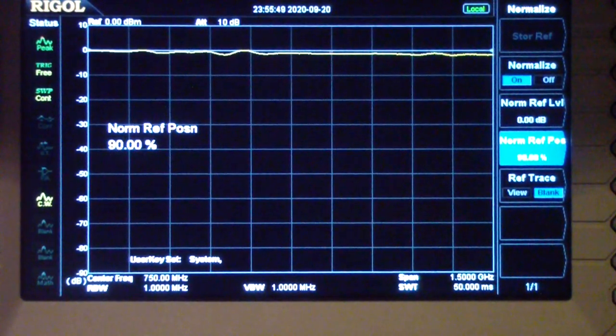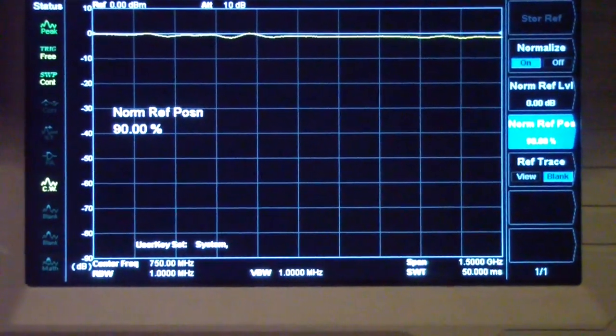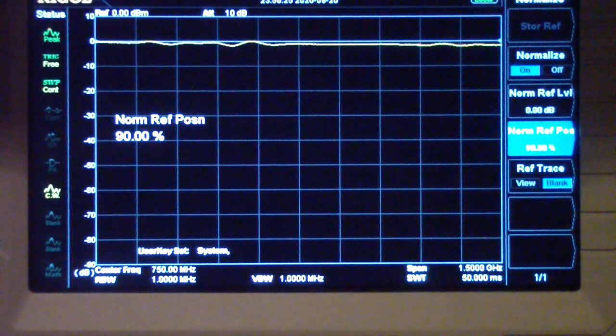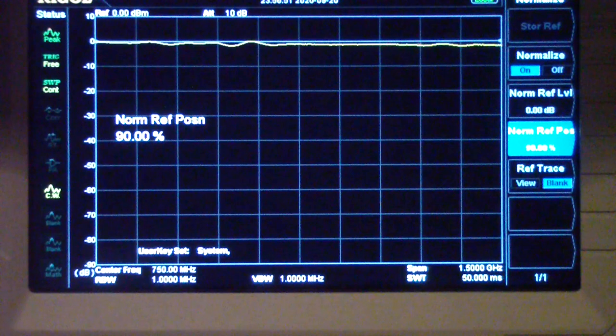Now I've inserted the step attenuator in place of the coupler, using exactly the same cables. Notice it has some frequency anomalies — what you'd call baseline anomalies. Those don't depend on which attenuation setting you have. But in a step attenuator you also have anomalies associated with each stage, and much of the cost of high-quality attenuators goes into eliminating as many of those anomalies as possible.